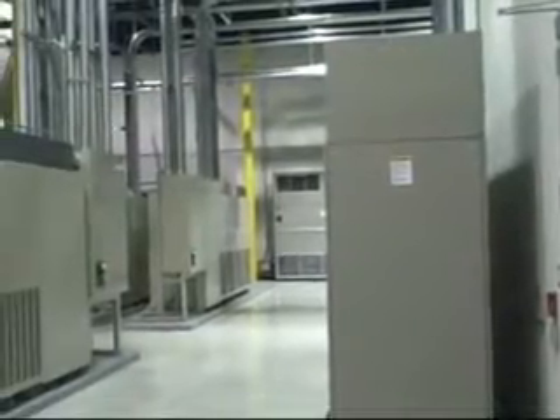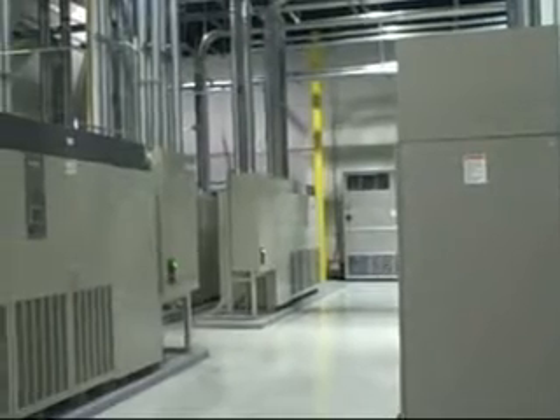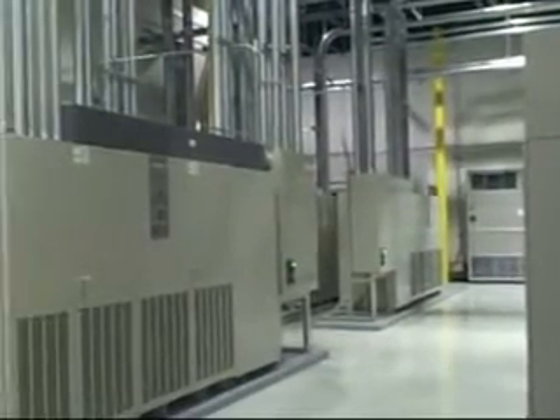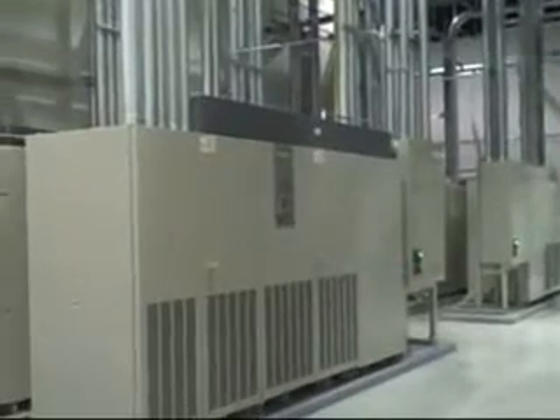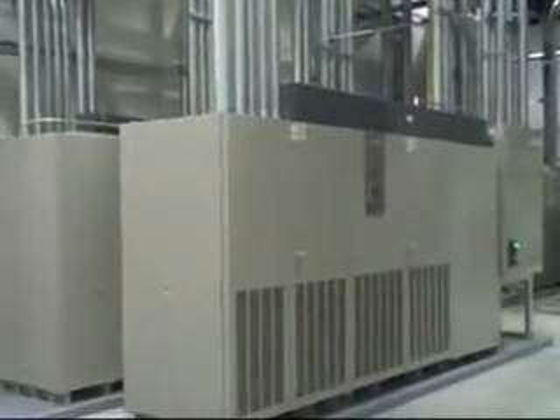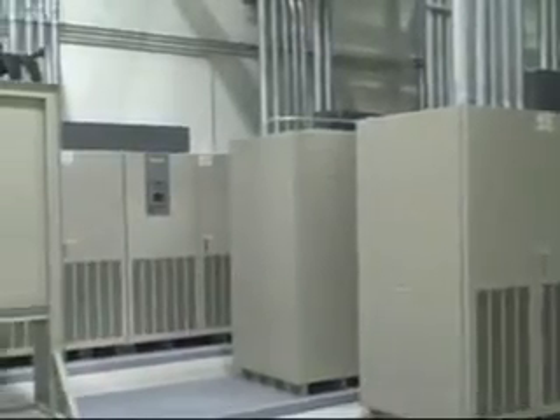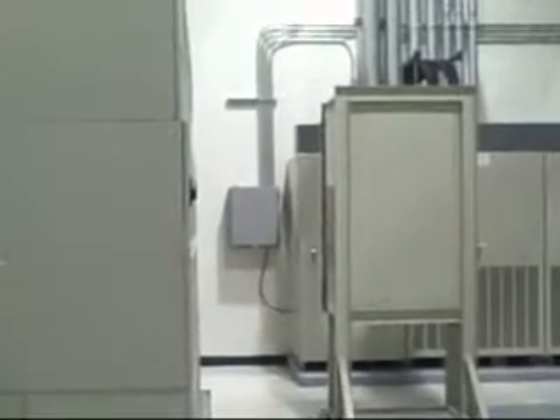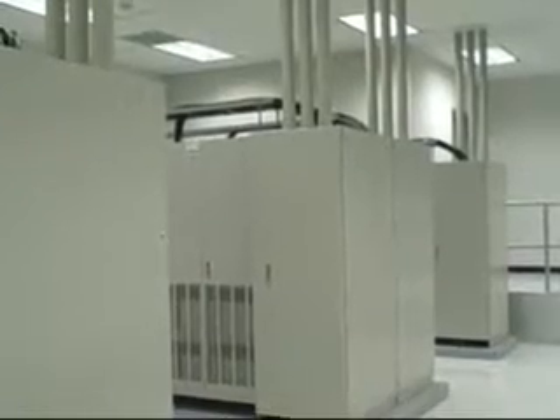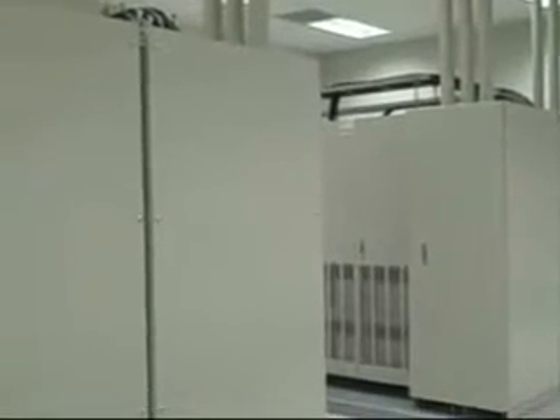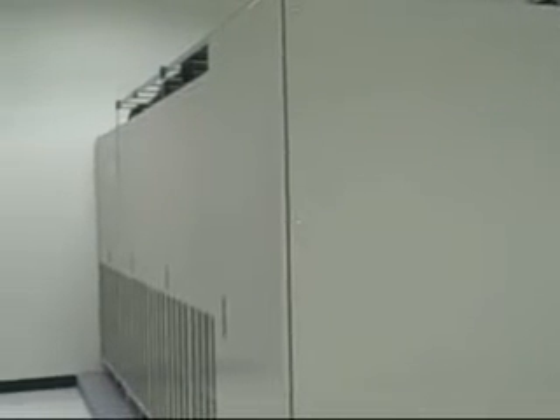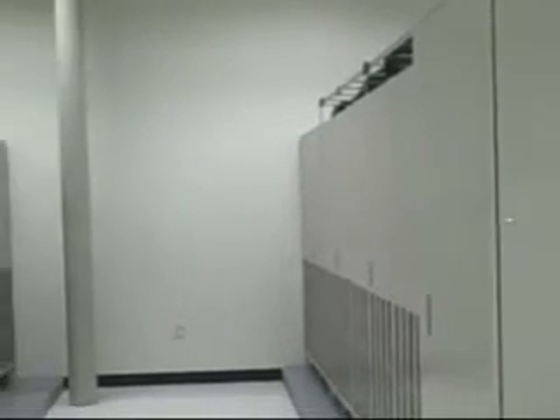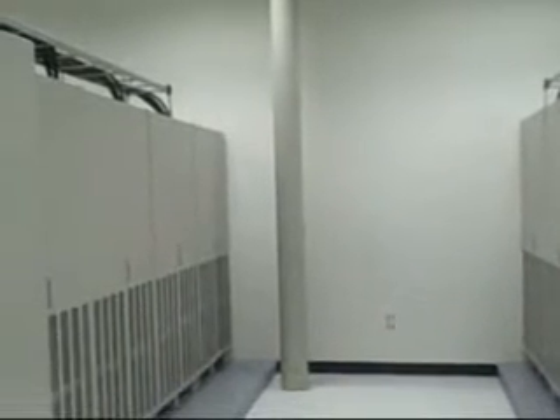Each phase of the data center has 4 UPS systems, with one there for redundancy purposes. Each UPS has its own string of batteries, and each string contains 4 cabinets of batteries. The Planet also runs its active UPS systems at a high utilization rate, and does it for a reason. Running the 3 units at near their capacity allows them to run much more efficiently, rather than if you were using parallel systems that you have to run the units at under 50%, which generally speaking UPSs are not very efficient at that low utilization.